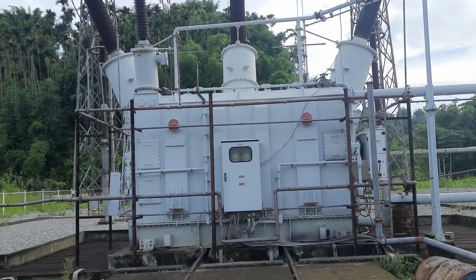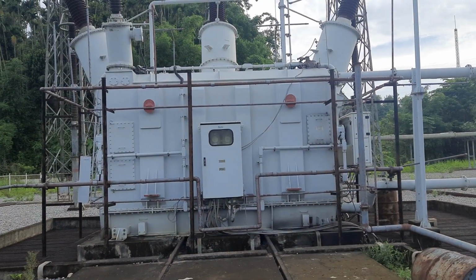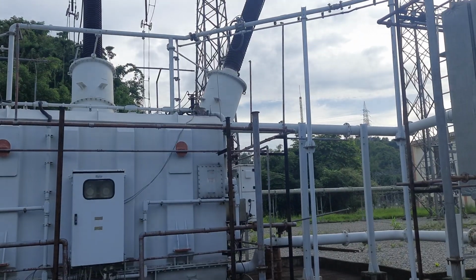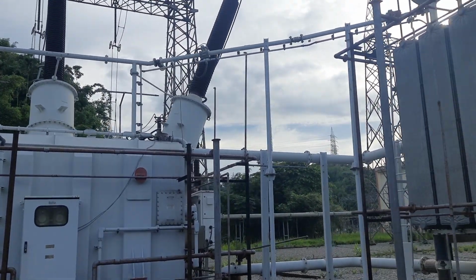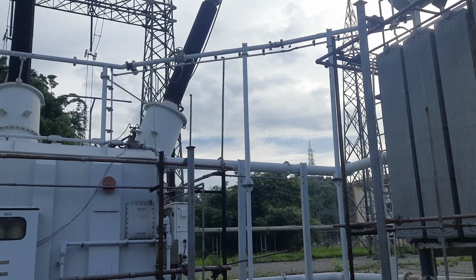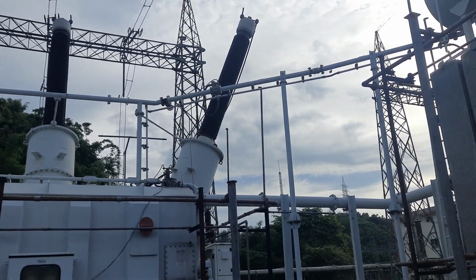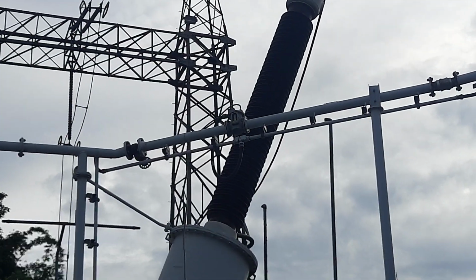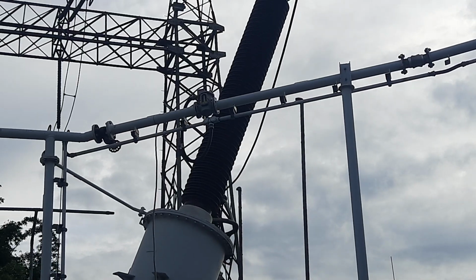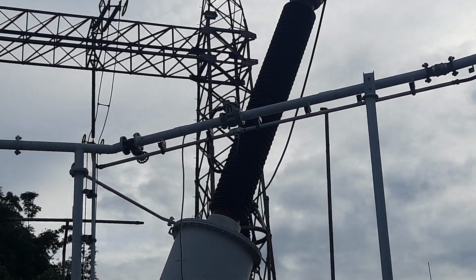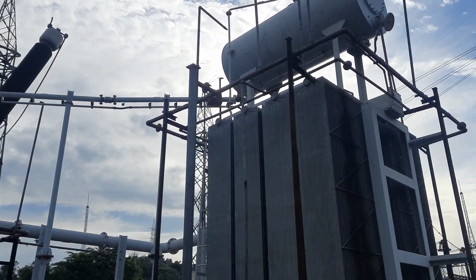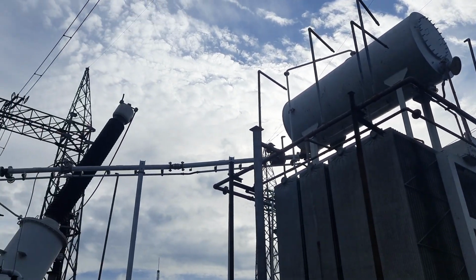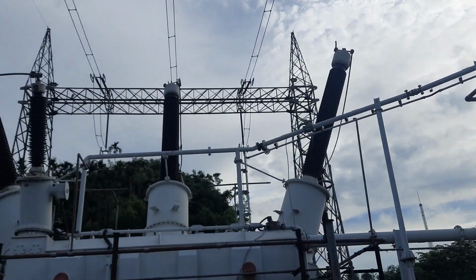Okay, so this is the reactor, but in this video our purpose is to locate the position of the Buchholz relay, which has been installed for detecting the formation of gas because of internal faults. So there it is, there is the Buchholz relay. Because the sun is coming from the side, it's not very clear, but there it is installed. There is the conservator tank, this is the radiator. It is installed between the conservator tank and the main tank.